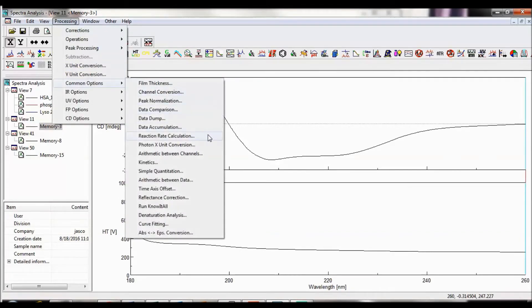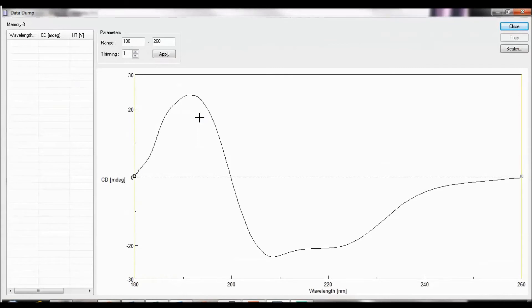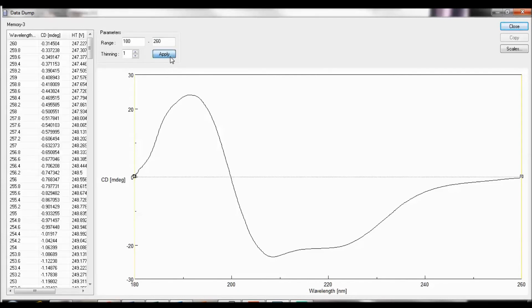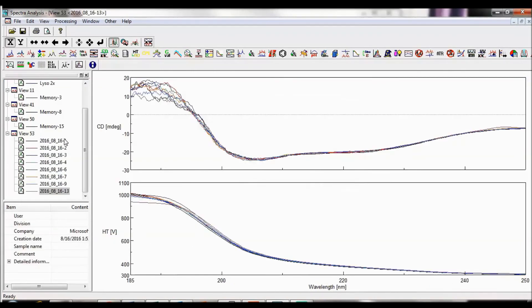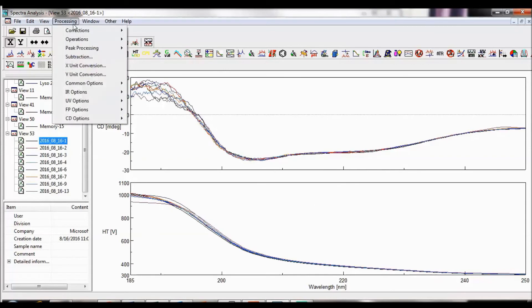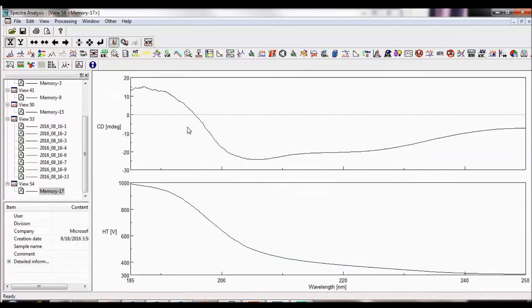Data comparison, reaction rate calculation, and the denaturation analysis functions are all discussed in separate videos. Data Dump displays CD values along with the values for each photometric mode selected for each wavelength. After setting the range of the X-axis, the thinning option will allow you to specify the intervals between data points that will be displayed. Apply executes the data dump process and displays the values to the left. These values can be copied to the clipboard. Data accumulation obtains the average spectrum of a series of overlaid spectra in the same view.